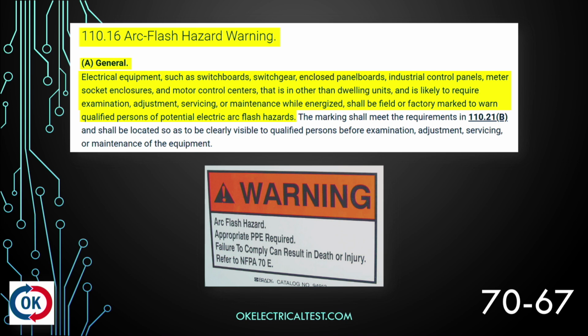Moving on, 110.16, speaking of orange, we've got arc flash hazard warning. So the picture there has got a sign with warning in orange. So our warning signs, we're going to talk about this here in just a little bit, but the warning signs need to have specific colorations, specific types of letters, sizes of those letters, and things like that. So here we're talking about an arc flash hazard warning.